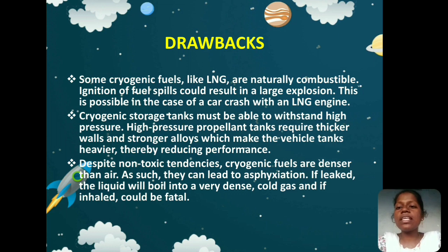Despite their non-toxic tendency, cryogenic fuels are denser than air. As such, they can lead to asphyxiation. If leaked, the liquid will boil into a very dense cold gas, and if inhaled could be fatal. So these are some drawbacks of the cryogenic liquid.